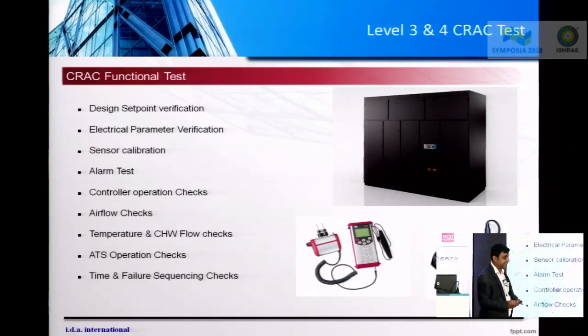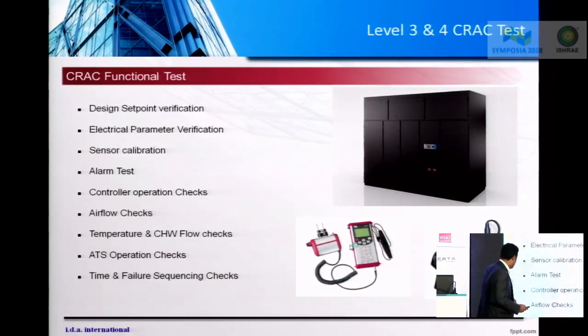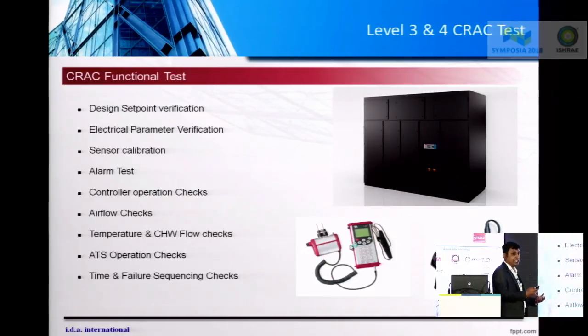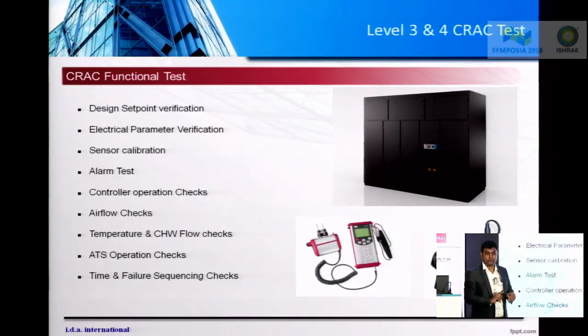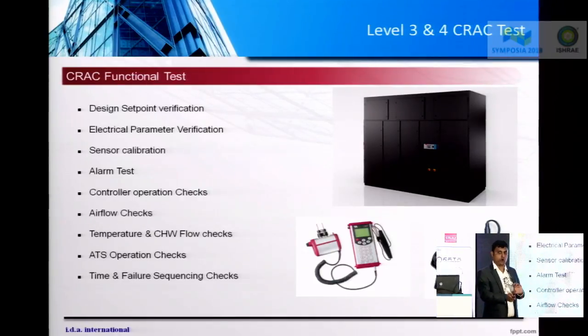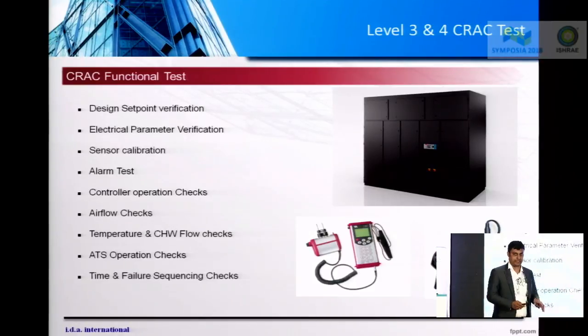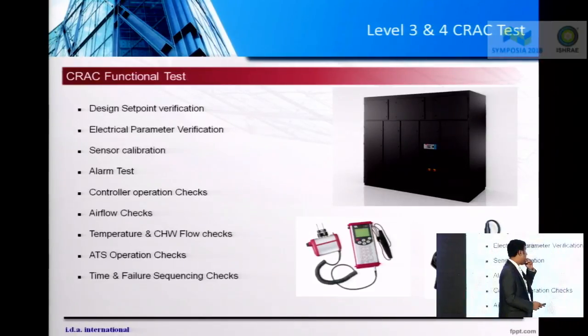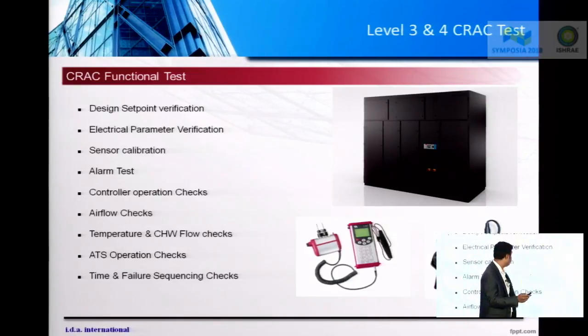Then you can verify the airflow rates. You can verify the temperature and the chilled water flow checks. These days you have an inbuilt ATS, so you can verify the changeover from primary source to secondary source, an auto changeover system. And then finally, time and failure sequencing. So this is basically the test that has to be carried out for a CRAC unit on site.